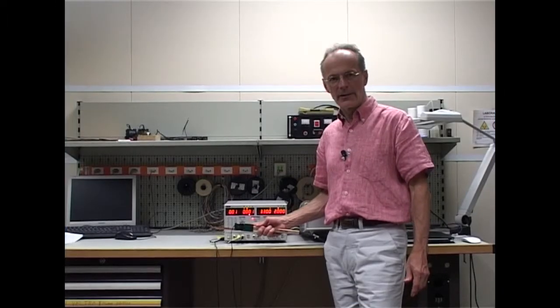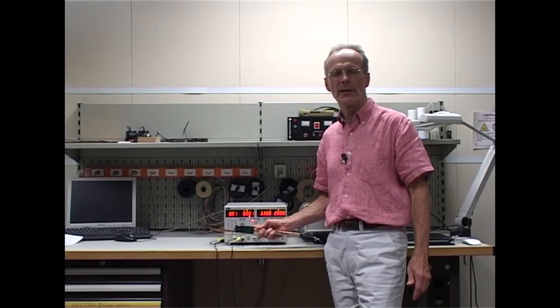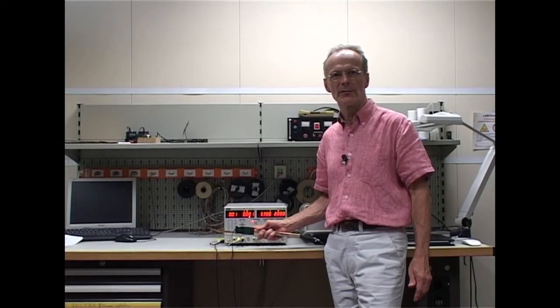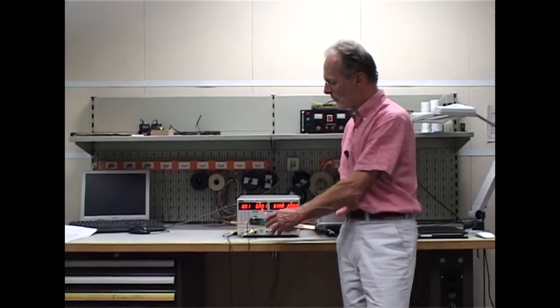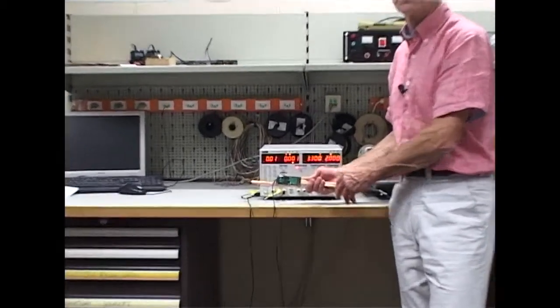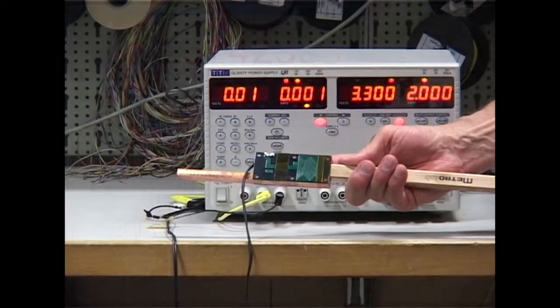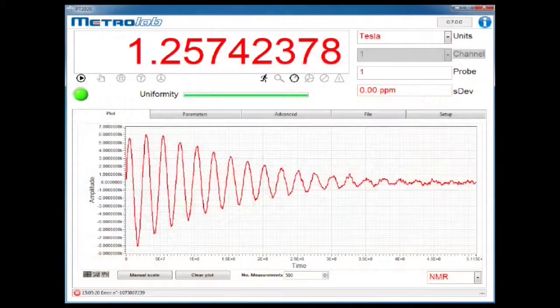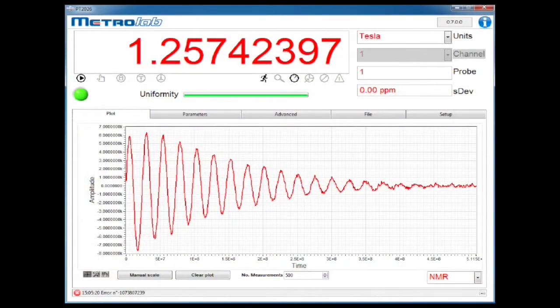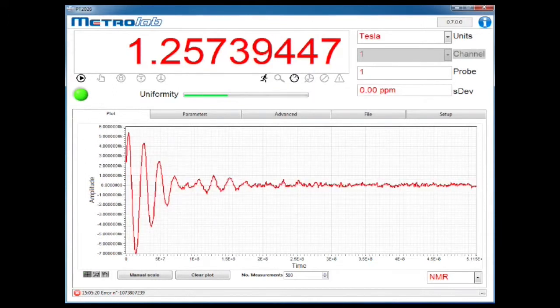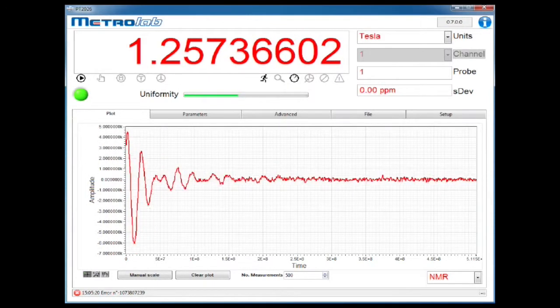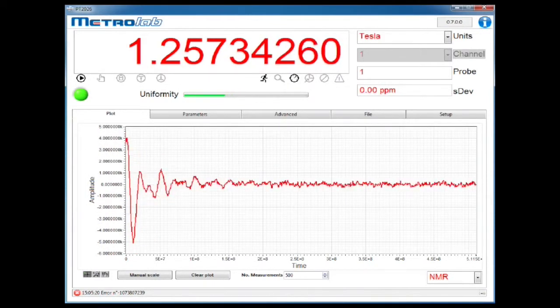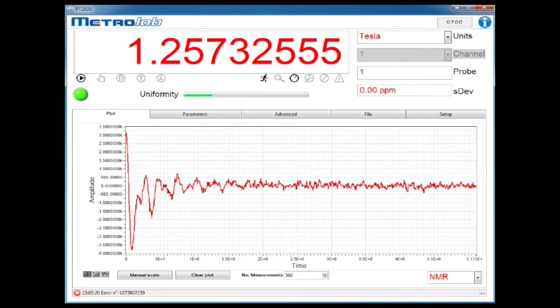I'd like to show you one more little experiment to demonstrate the effect of inhomogeneous field. To do this, we mount a gradient coil on one of our probes. As we increase the current in the gradient coils, the NMR signal decreases, and the uniformity indicator decreases, until the instrument can't measure anymore.